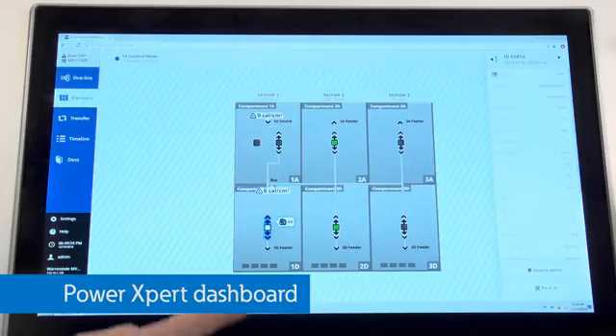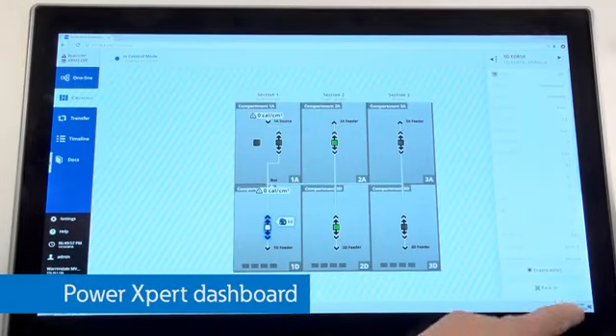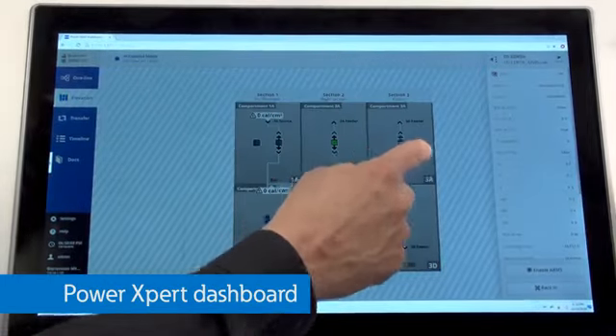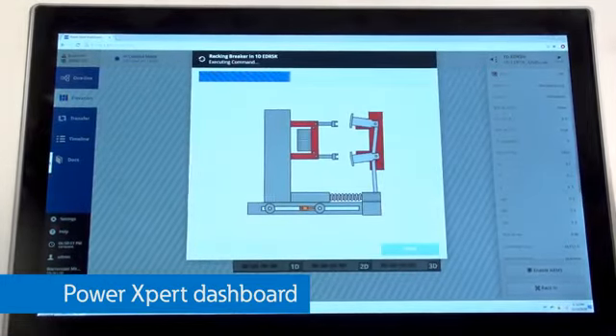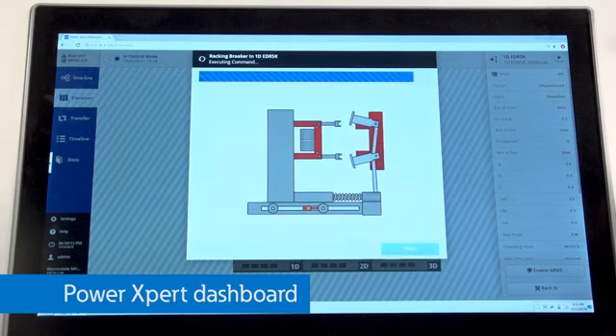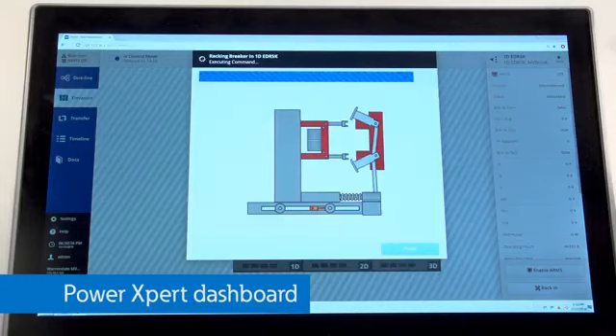More and more we are asked by our customers to provide equipment that can be remotely operated or controlled with an HMI to reduce exposure during arc flash events. This Power Xpert dashboard is a perfect solution to not only see what the arc flash levels are, but you can monitor power flow and control the equipment.